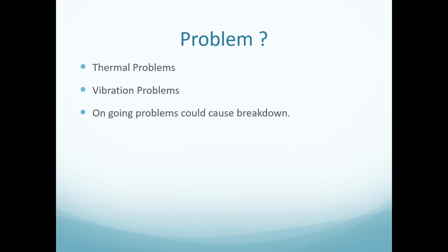When servers go to production, one of the major problems they encounter is that the components inside the server must be thermally tested to see if they can be supported, especially solid-state drives and processors. The server's mechanical hardware must be able to function at the range of ambient temperature. Thermal tests provide the necessary data to determine whether components will be able to function inside the server chassis at the highest performance.